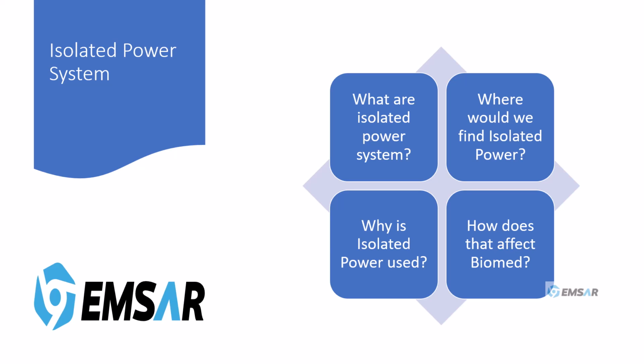Well, isolated power systems are safety systems that isolate rooms, such as surgical suites, from earth ground and provide an early warning alarm when an electrical fault is noted. It decreases electrical shock potential. The system is composed of 2 ungrounded conductors. In the event of a fault, it sounds an alarm or it opens a circuit breaker, and the patient or doctors are not harmed.